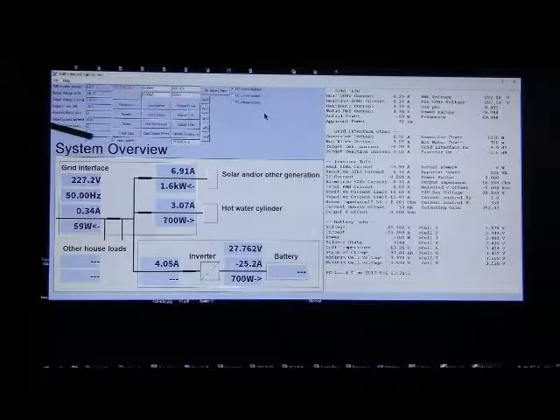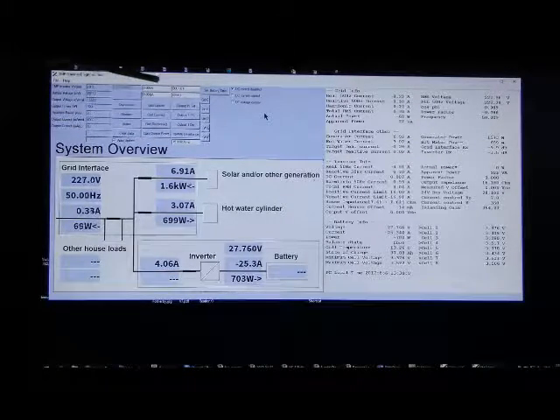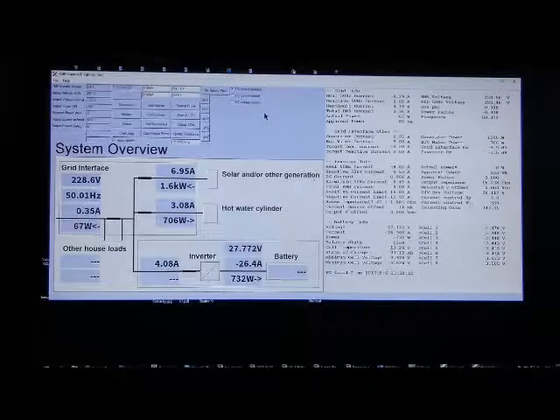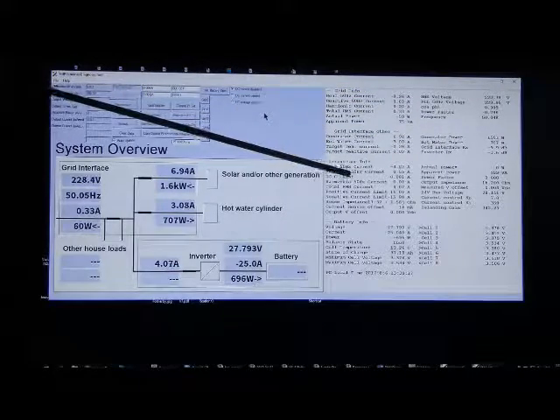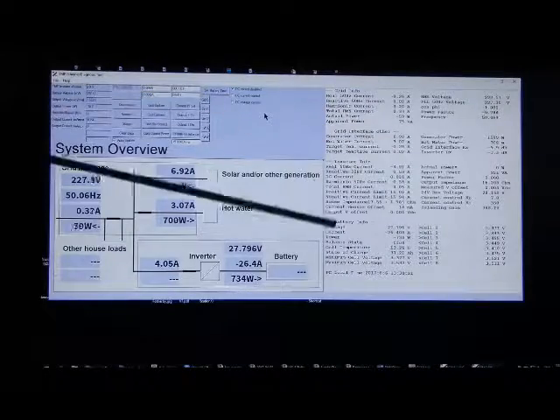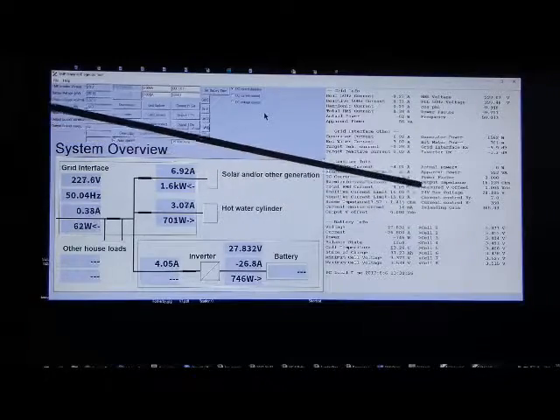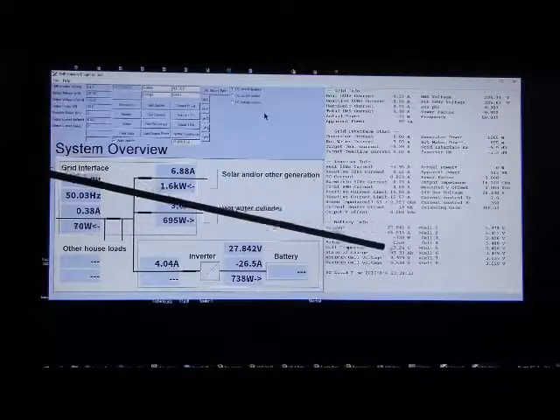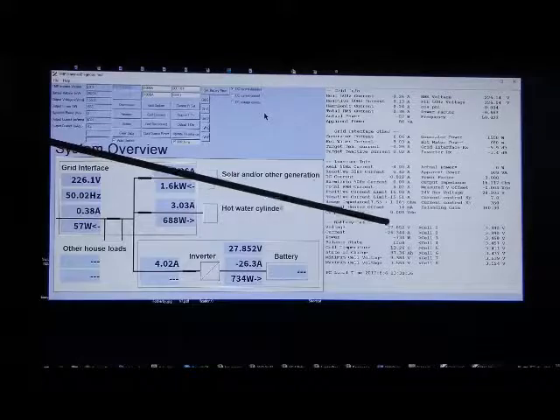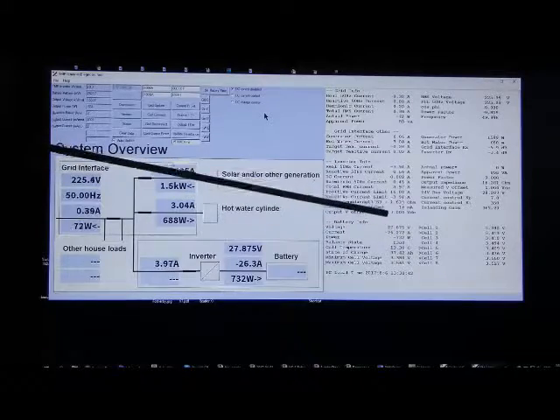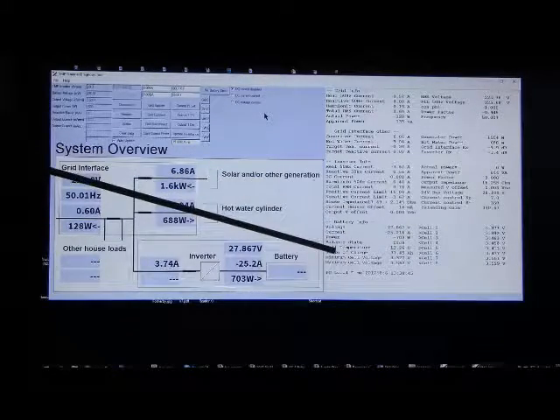Up in this region we have some control sections, things for setting the real and reactive current coming into the house. Over here we have more detailed information about the grid interface and the inverter, and down here we have information on the battery. We have the voltage of all 8 cells, we have the current going into or out of the battery, and also the voltage of the highest voltage cell and the voltage of the lowest voltage cell, which are used to restrict the charge and discharge current when the battery is fully charged or fully discharged.